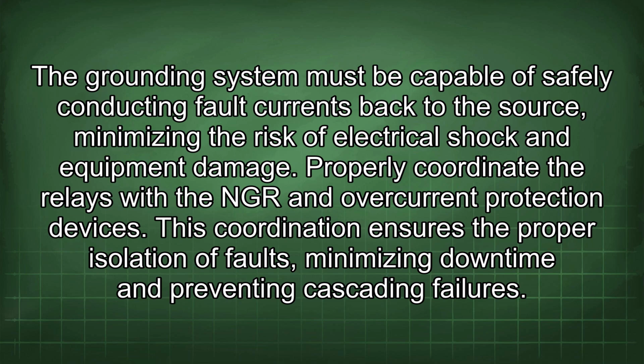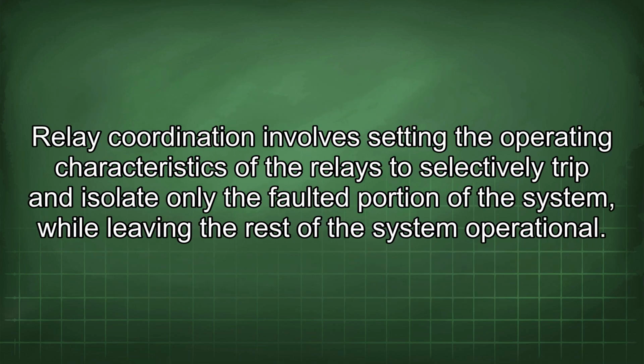Properly coordinate the relays with the NGR and overcurrent protection devices. This coordination ensures the proper isolation of faults, minimizing downtime and preventing cascading failures. Relay coordination involves setting the operating characteristics of the relays to selectively trip and isolate only the faulted portion of the system, while leaving the rest of the system operational.